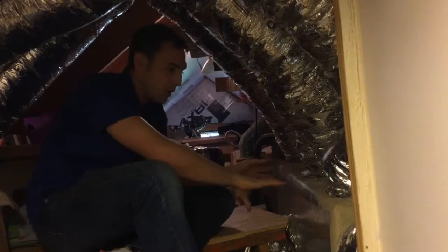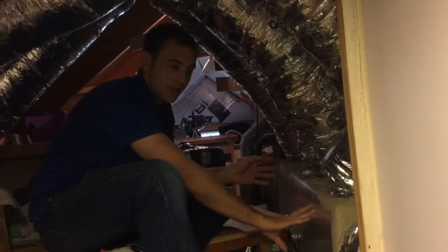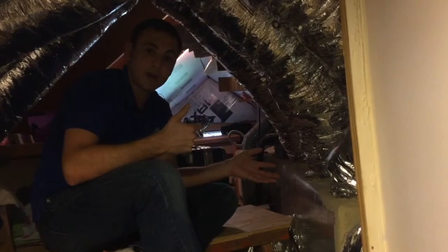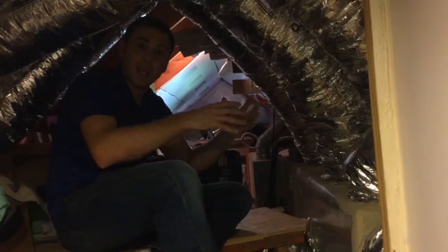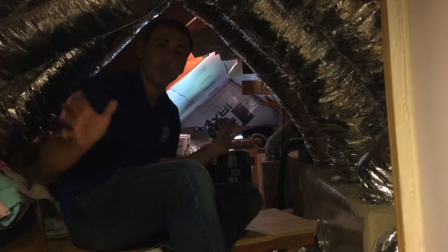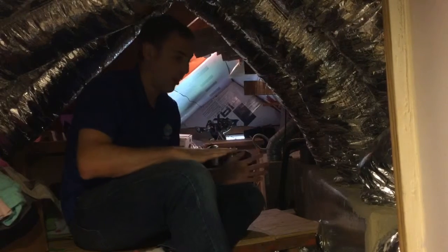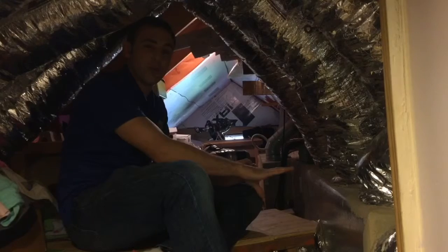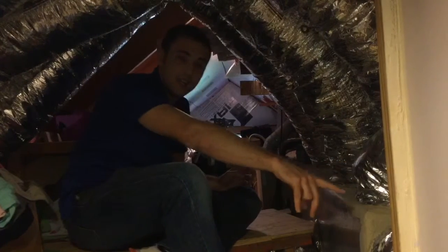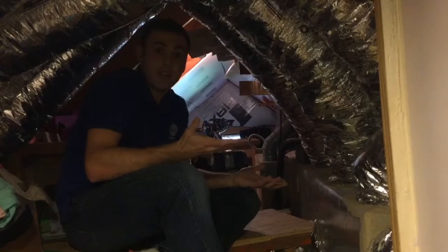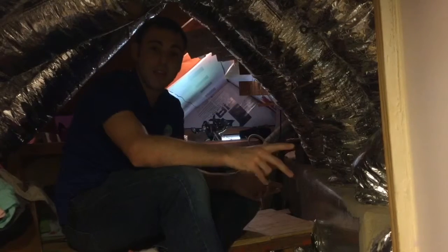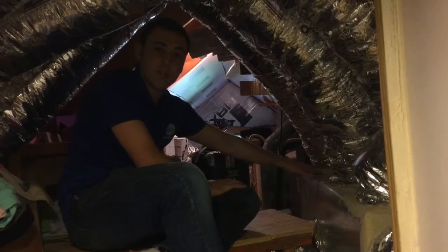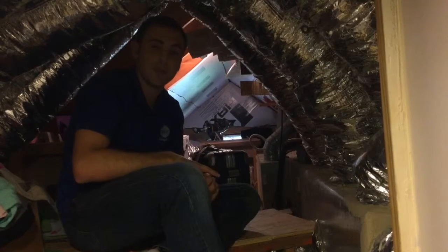And so where you put your flex duct on this supply plenum affects how much airflow is going to come out. So the idea is that this plenum is going to be equally pressurized, right? In theory, the plenum is pressurized equally, and then the duct sizing determines how much air goes to which room or place from there. The issue with this particular situation is they have ducts coming off the end of the plenum. And the problem there is that the plenum now can't pressurize. All of that air just goes straight down and straight through the ducts that are on the end, which actually sort of starves the ones that are at the beginning because there's not an equal pressure buildup inside the plenum.